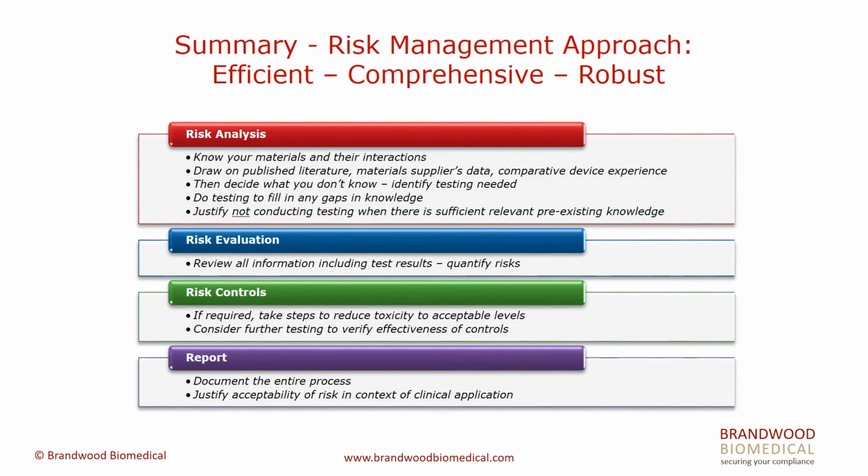So in summary, this risk management approach to biological evaluation is essentially efficient, it's comprehensive, and it's robust. It begins with a risk analysis of understanding the materials and the interactions, drawing on the published literature, material supplier data, comparative device experience, and deciding what you don't know.